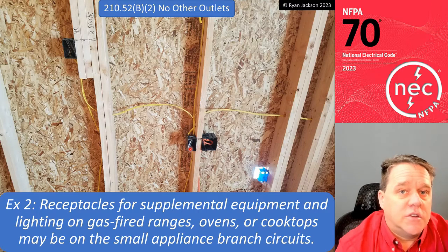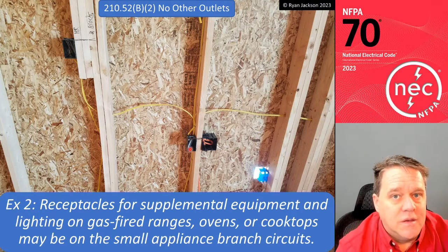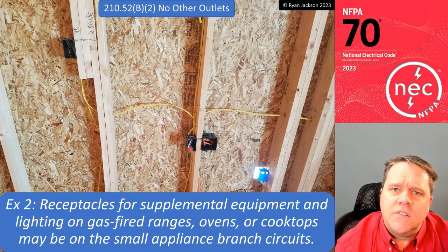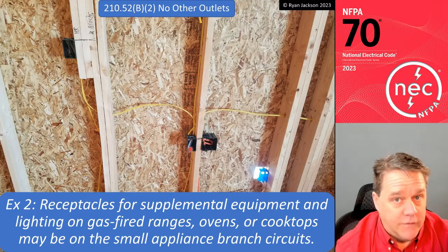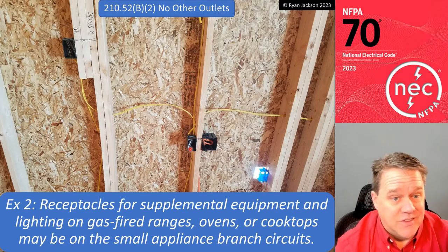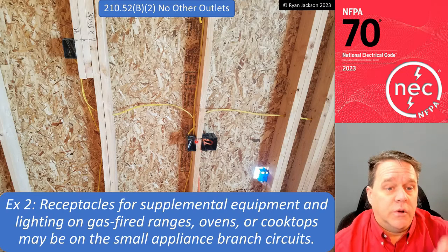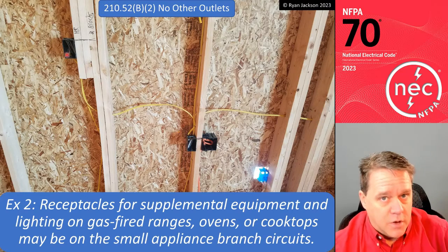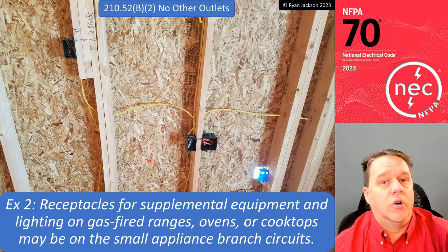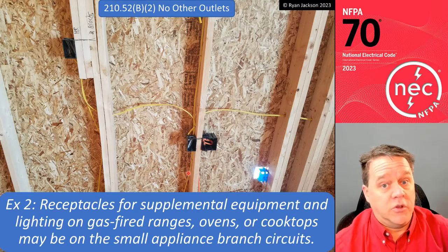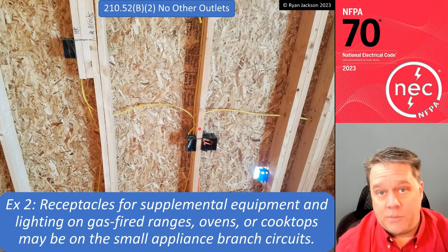If you go to section 422.16 B4, I think it's item number 5, it says that the microwave, if it's cord and plug connected, has to be on its own circuit with nothing else, not even the gas igniter. So put the gas igniter on the small appliance branch circuit. Don't put it on the microwave circuit, and obviously don't put the microwave on the small appliance branch circuit.